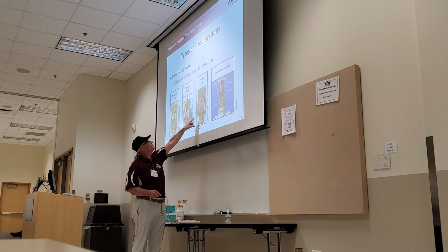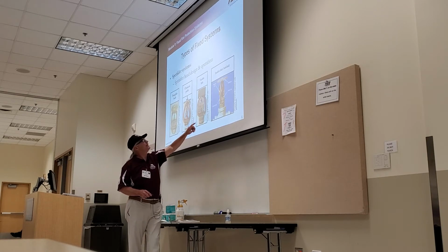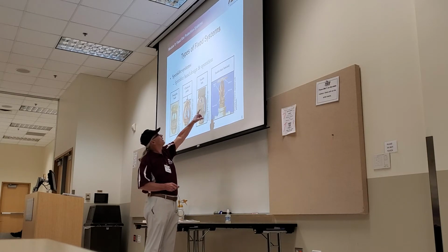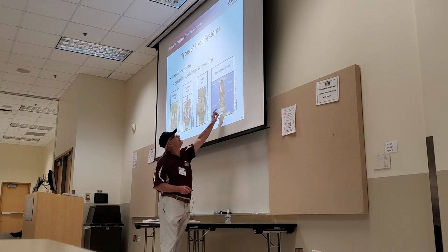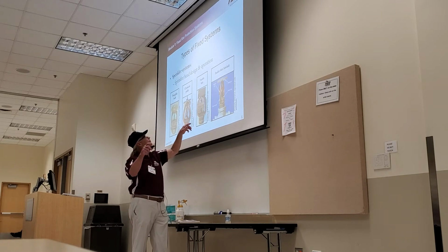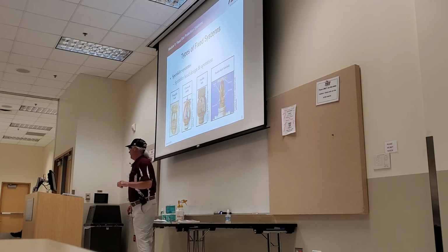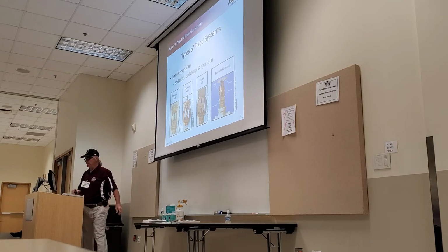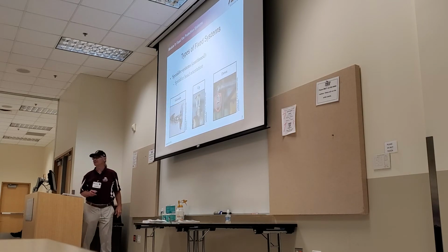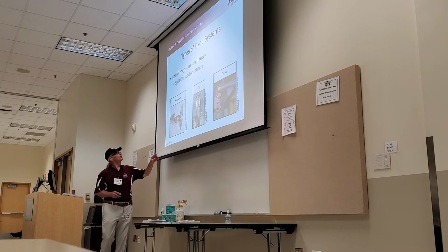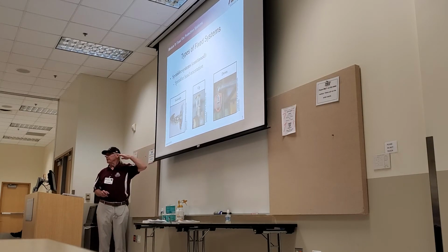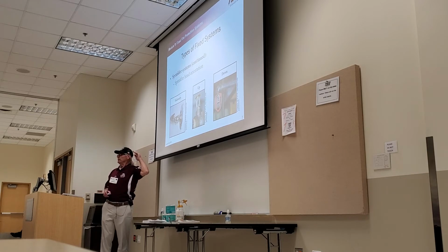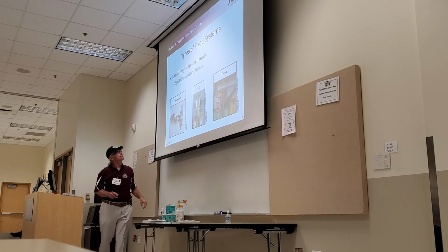See the sidewall, the deflector on that one, it's that same fusible link. And then here's an upright also. Here's a frame arm, the valve cap, it's a 7/16 opening, and then you have the deflector on top, and that rolls it out, and there's a fusible link. In your hotel rooms, they put sidewalls in, and they put signs on that say, "Do not hang your clothes here." Because if you knock that out, and it doesn't take much, it'll shoot about 20 feet out. So it's right by your door, and it shoots all the way to the window on those things.